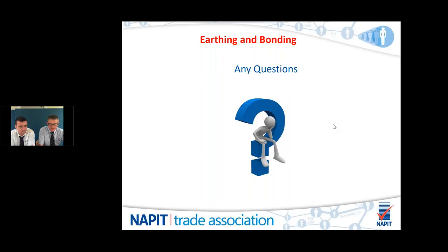The on-site guide in a domestic dwelling is sort of a belt and braces situation, whereas if you put 25 mil tails in and a 16 mil earthing conductor, there will never ever be any comebacks at all. Over the top it may be, yes, but there's going to be no problems that you will envisage in the future. Anything less than a 16 mil main earthing conductor and anything less than 25 mil tails, then you're guaranteeing by the signing of the certificate that you're happy with that installation and nothing will happen.